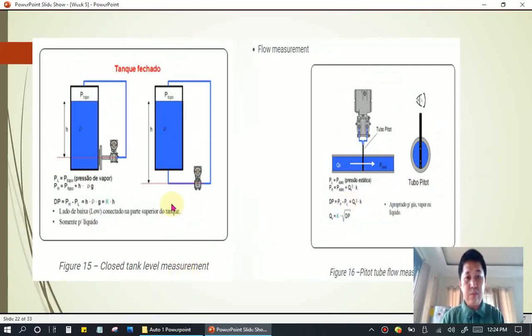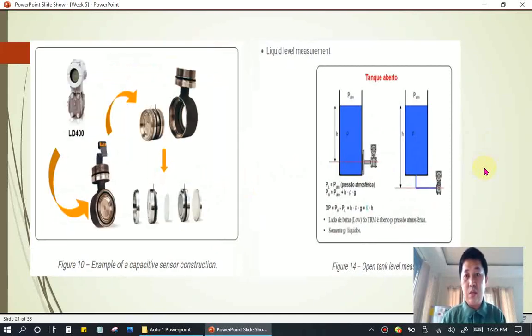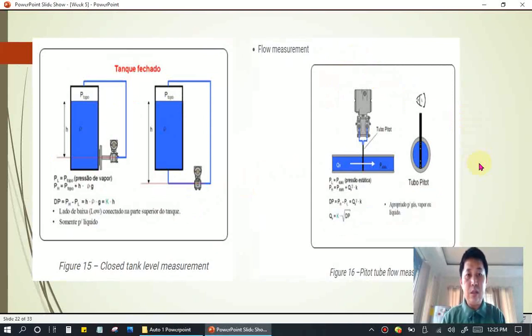Next, closed tank level measurement. The difference from the open tank is that here there is a cover on top. There should be fluid in here at the same level. You cannot read it here, otherwise this is a sight glass. Some of the media here is air, and the liquid is only up to this point. But you can read the level of this tank through this level measurement gauge.